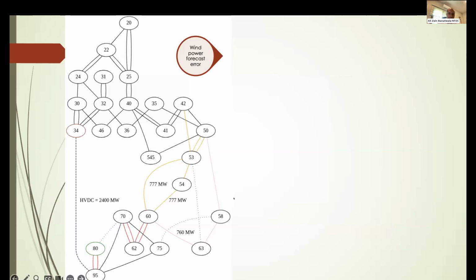It was operating at capacity, let's say 2.4 gigawatts or around 4 gigawatts total. And then we got 600 megawatts of wind. So this created low frequency oscillations, as I showed you previously, on the AC network, which then led to voltage instability, as power is flowing over this very, very narrow corridor, extremely large amounts of power. It pushes the voltage down.